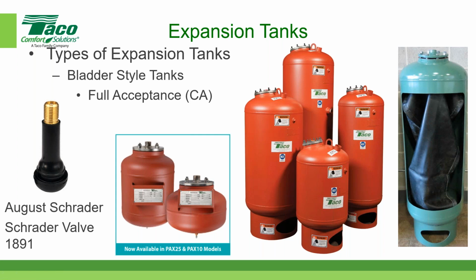Initially they purge the air out of the system. If you have an air and dirt separator, like a 4900 from Taco, it's very good at removing air. So as soon as that bladder tears, the air wants to go into solution into the water, because the water has no air in it. We've taken all the air out with the air and dirt separator. And so it quickly goes into solution, which means that the tank keeps filling up with water and eventually the tank becomes waterlogged. So if I push the little Schrader valve right here in the top, and I get water out, then that's a pretty good indication that the tank is waterlogged and that the bladder has failed. It's not an absolute, but it's a pretty good indication.